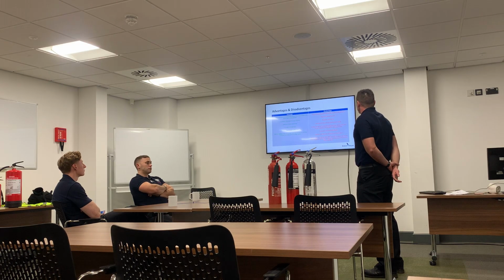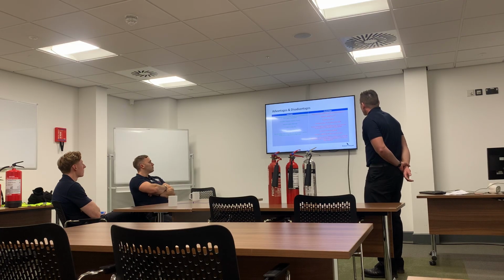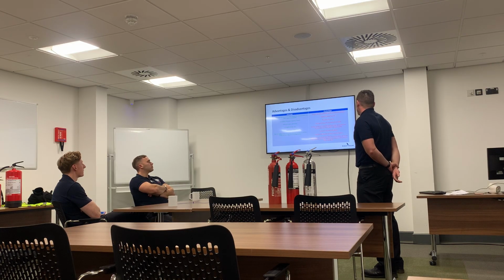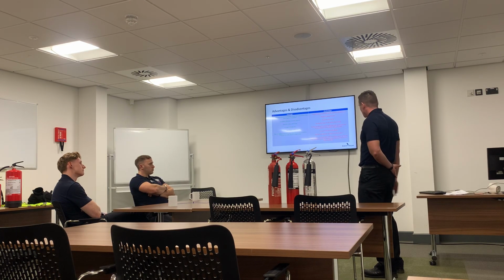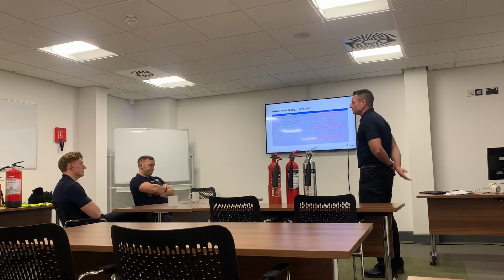And then there's excessive noise during discharge, and impaired visibility when working in confined spaces, because it creates that cloud of CO2 as a gas, and when used in a confined space will form a dense vapour which will impair visibility, and in high enough concentrations can become an active asphyxiant. So asphyxiant obviously takes your breathing away. The benefits of it could affect us.